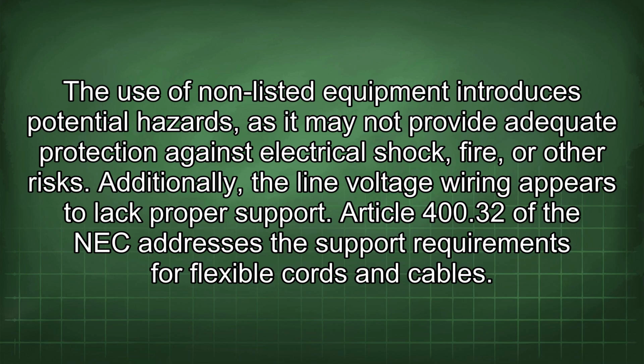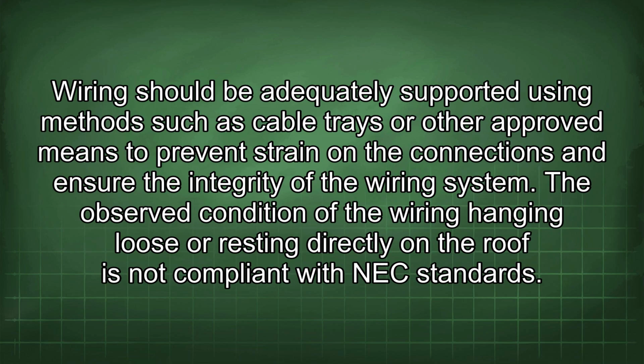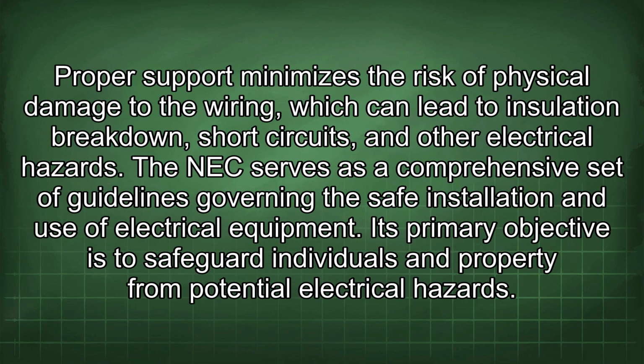Article 400.32 of the NEC addresses the support requirements for flexible cords and cables. Wiring should be adequately supported using methods such as cable trays or other approved means to prevent strain on the connections and ensure the integrity of the wiring system. The observed condition of the wiring hanging loose or resting directly on the roof is not compliant with NEC standards. Proper support minimizes the risk of physical damage to the wiring, which can lead to insulation breakdown, short circuits, and other electrical hazards.